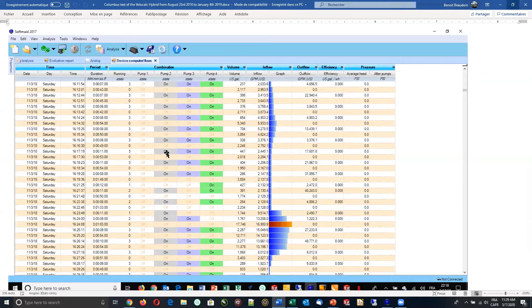And we never received any kind of alarm, because the events were just too short for this to happen. It was switching between the emergency off switch at the bottom of the well, which was telling exactly the opposite of the level sensor.